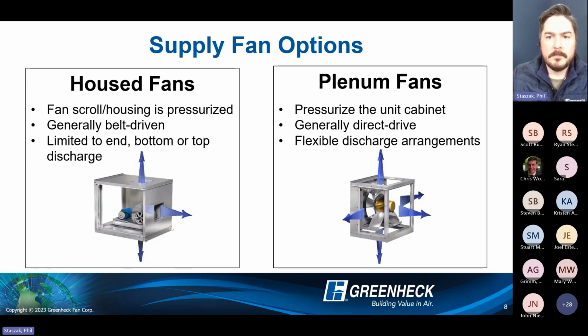And then other things that we see here as far as benefits on the plenum fan, I mentioned this already, that scroll fan needed to be built in a certain arrangement and you were limited to either end, top, and bottom. With a plenum fan, since we're pressurizing the cabinet, basically just give us an opening and now we can do left and right side discharge as well.